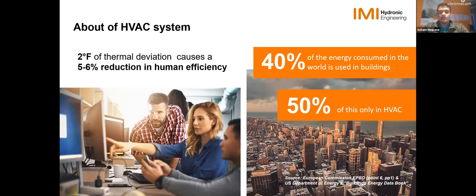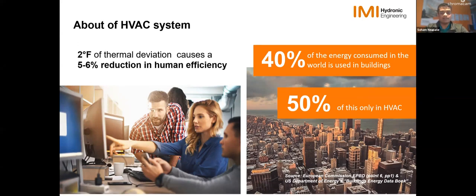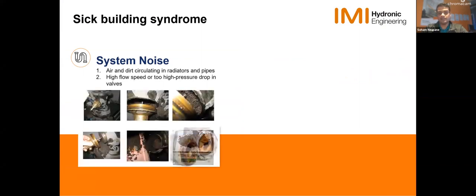And when we don't look into the proper design of HVAC systems, what we're going to see is sick buildings, basically. You're going to have huge temperature gradients and fluctuations in your building. Some parts are going to be too hot, some too cold, and this will in turn result in what we call sick building syndrome. The first thing you'll start hearing may be system noise. If there's air and dirt in the pipes, and too high flows or too high pressure drop, you're going to start hearing noise coming from the ceiling, which no one likes. And similarly, you're going to see dirt gather on the pipes. I don't think this is a new sight for anyone here. You go to a job site, and it's common to see issues with dirt accumulation in a system.